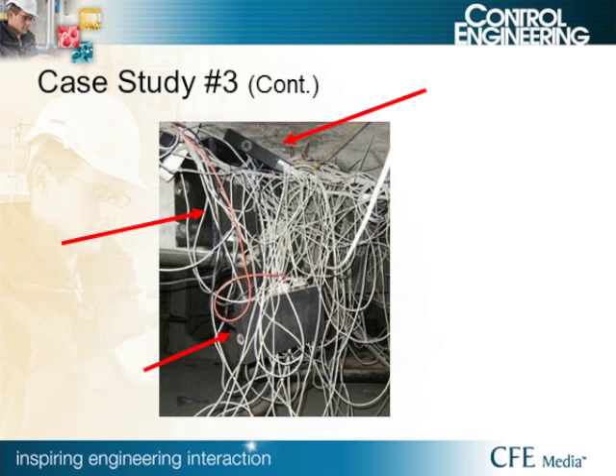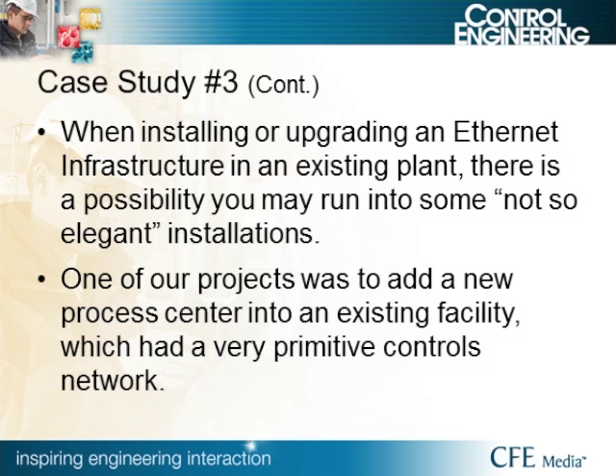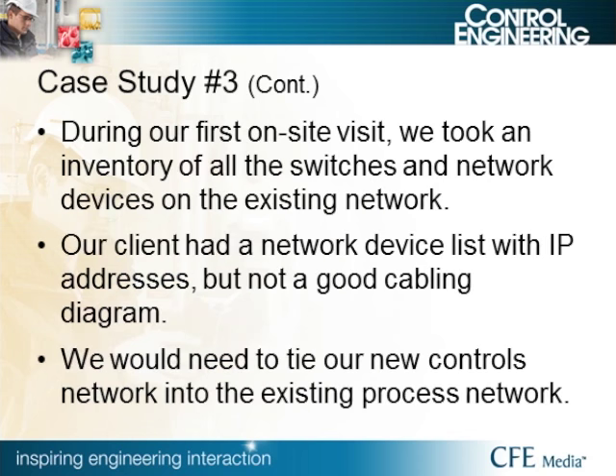Looking at an example of a messy switch installation — during this project we saw something maybe not quite that bad, but there were switches up in the ceilings that we didn't see right away. When you're installing or upgrading Ethernet infrastructure into an existing plant, you're going to see some not-so-elegant installations. A lot of stuff in older plants just keeps growing and growing, starting from a very rudimentary network and getting built on and built on. It's really worth the time to go through those installations thoroughly.